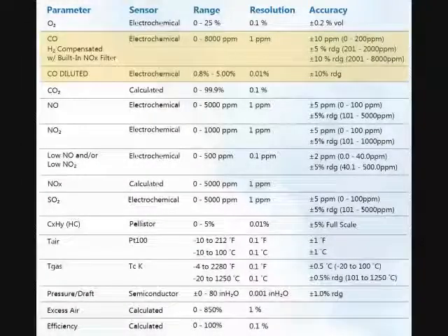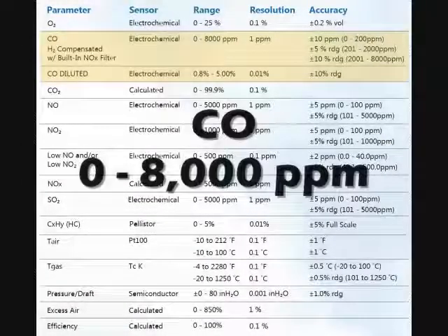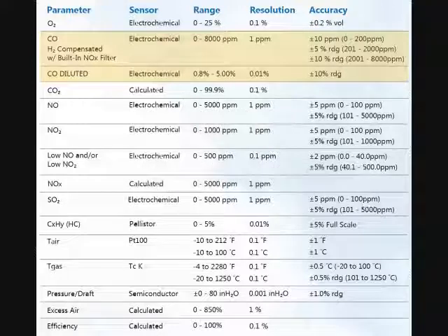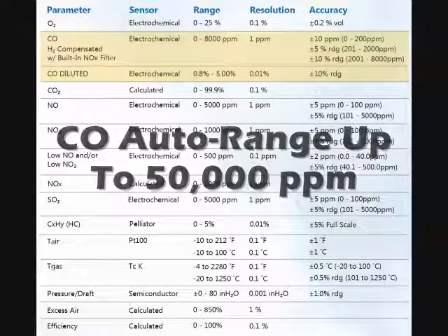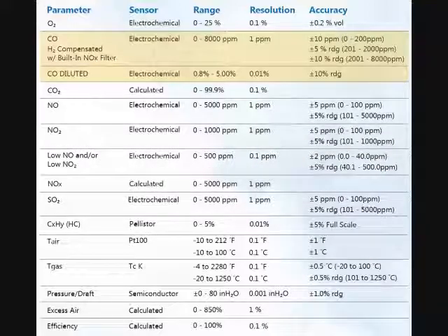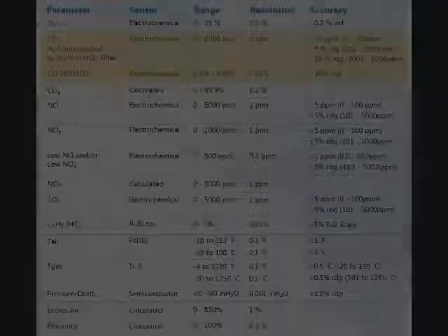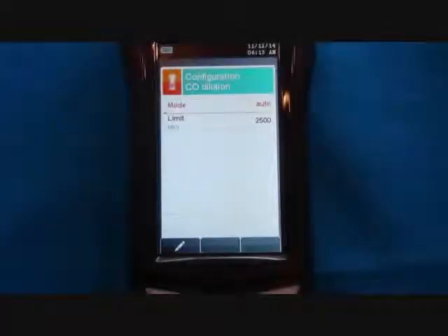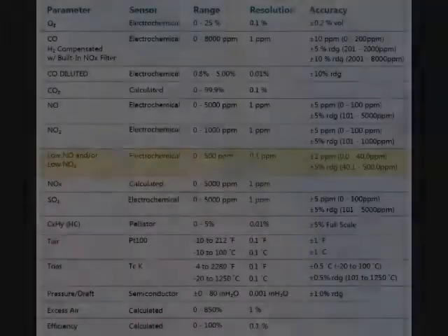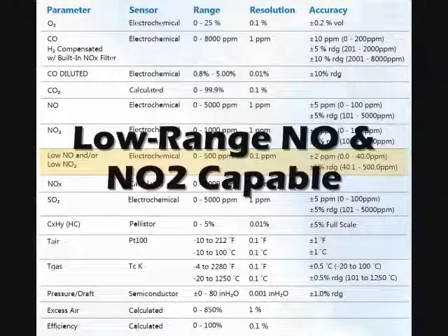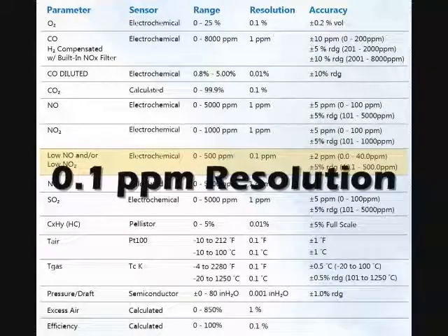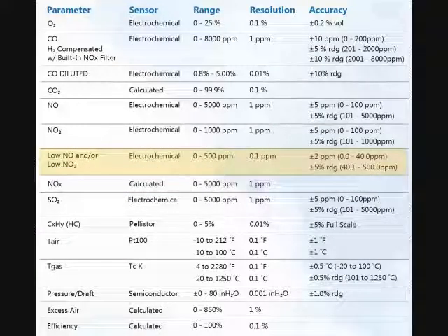The CO sensor has a normal measuring range of 0 to 8,000 ppm. This sensor has a dilution auto-range feature that allows for CO measurements as high as 50,000 ppm while protecting the CO sensor from oversaturation. The CO auto-range has a user-selectable threshold that is automatically enabled and disabled. The NO and NO2 sensors can be configured for low ranges with 0.1 ppm resolution when low NOx measurements are required.